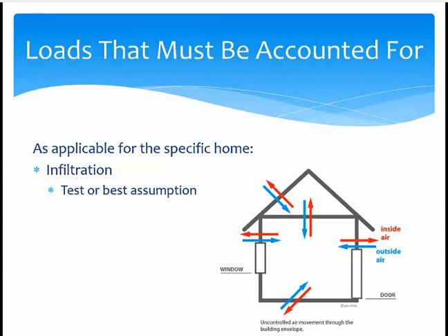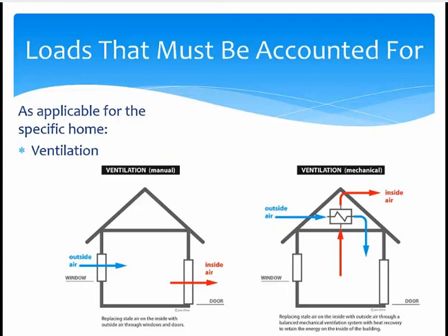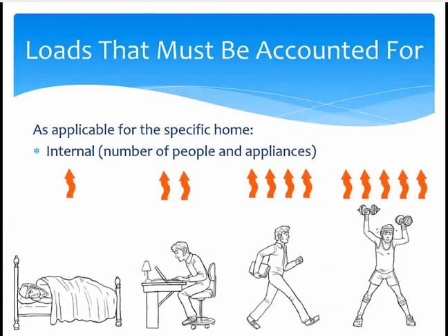The most precise way to get the infiltration load is to measure it directly using a blower door. But sometimes that's not possible — for example, if the home's not built yet. In that case, Manual J has some default values that can be used based on construction assumptions. Next is the ventilation load. Ventilation is simply replacing the inside air with outside air, which can be done manually, like by opening windows, or mechanically, like with a ventilation system. The diagram shows both ventilation done manually on the left and ventilation mechanically on the right.